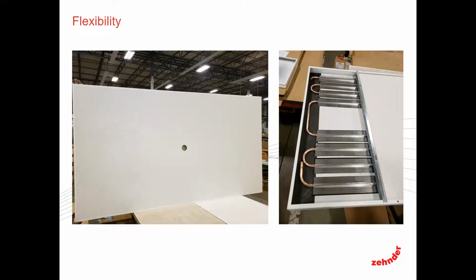Now, one of the things I want to make mention about here is when designing a system, an overall space, what you want to try to do is minimize the number of variations on the job. So if you can standardize on a center location for fire suppression, same number of passes on the same end, same panel size repetitive over and over again, that's really what's going to help keep your overall cost down on the job, because the last thing you want to have is the installer having 50 or 60 or 70 unique panel types on the job that go in very specific locations.